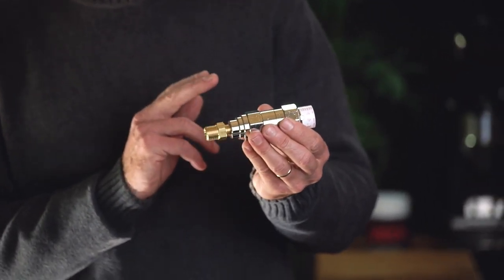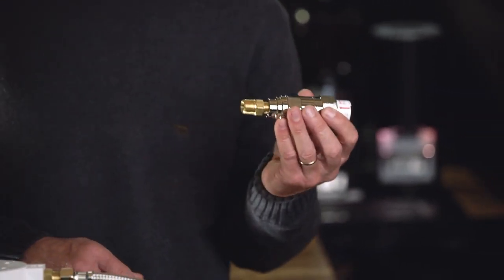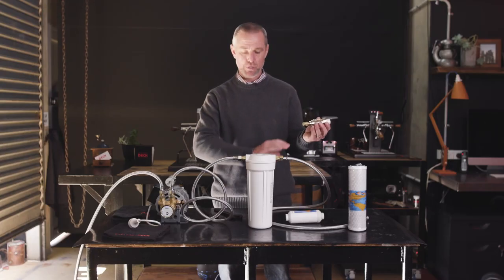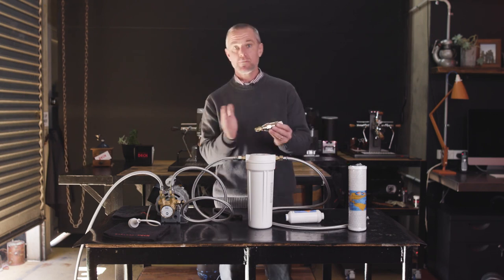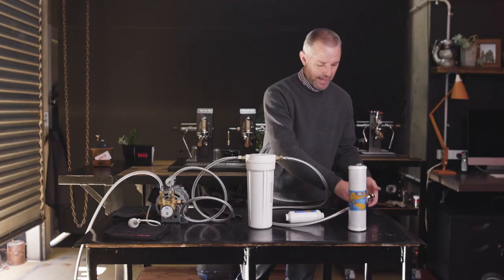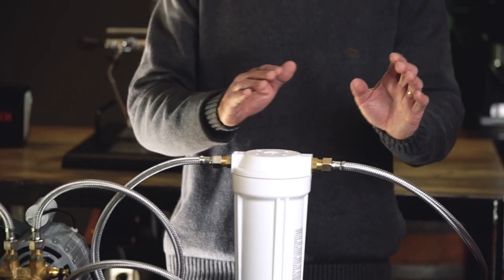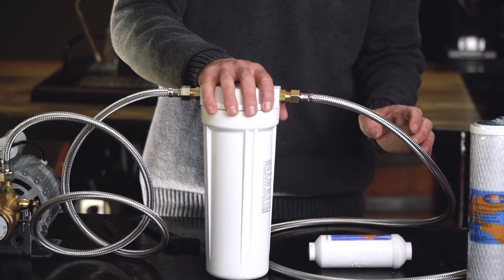350 kPa or three and a half bar of pressure is what that is designed to bring your mains pressure down to. You can also have a check valve in that, but the main idea is to have a pressure maintained at 3.5 bar. From there, we come into the water filter.